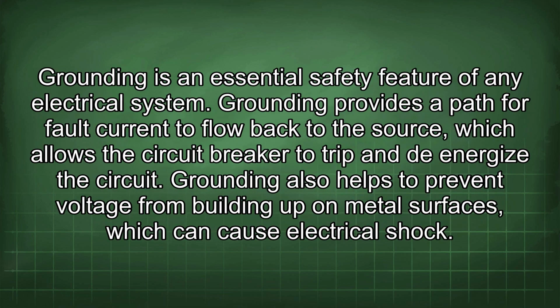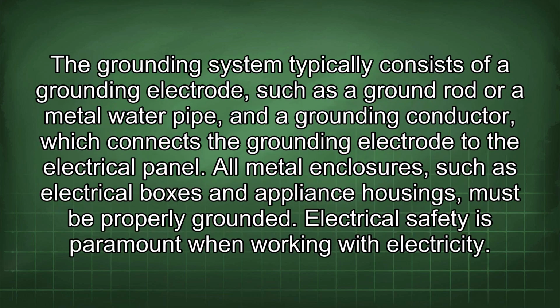Grounding is an essential safety feature of any electrical system. Grounding provides a path for fault current to flow back to the source, which allows the circuit breaker to trip and de-energize the circuit. Grounding also helps to prevent voltage from building up on metal surfaces, which can cause electrical shock. The grounding system typically consists of a grounding electrode, such as a ground rod or a metal water pipe, and a grounding conductor, which connects the grounding electrode to the electrical panel. All metal enclosures, such as electrical boxes and appliance housings, must be properly grounded.